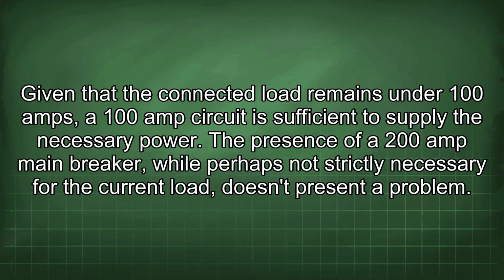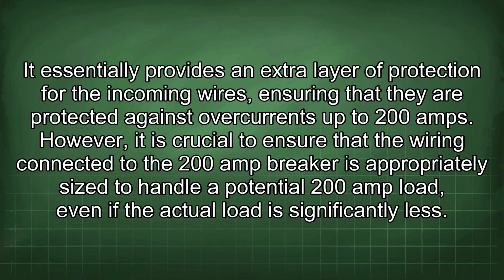The presence of a 200 amp main breaker, while perhaps not strictly necessary for the current load, doesn't present a problem. It essentially provides an extra layer of protection for the incoming wires, ensuring that they are protected against overcurrents up to 200 amps. However, it is crucial to ensure that the wiring connected to the 200 amp breaker is appropriately sized to handle a potential 200 amp load, even if the actual load is significantly less.